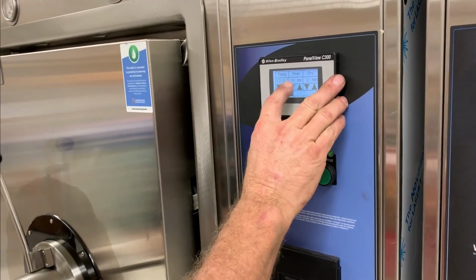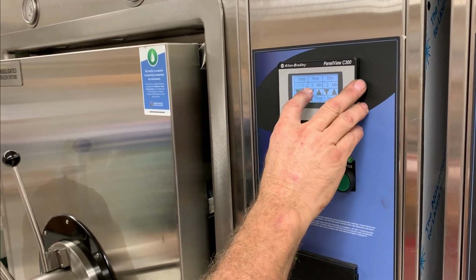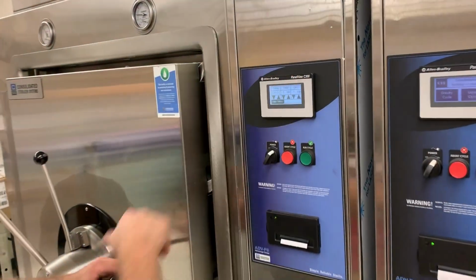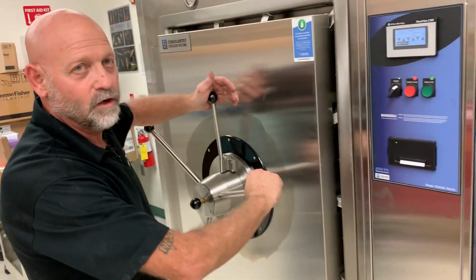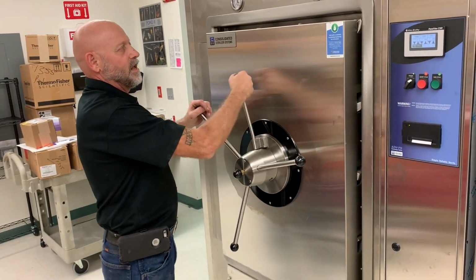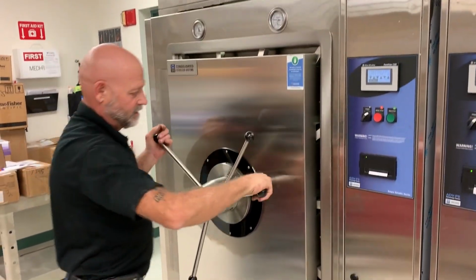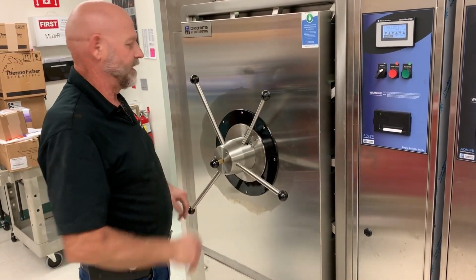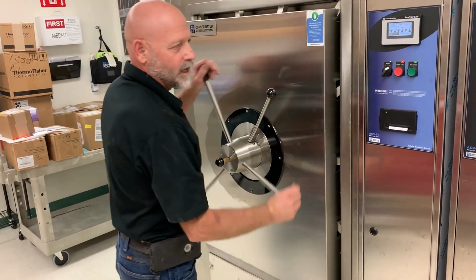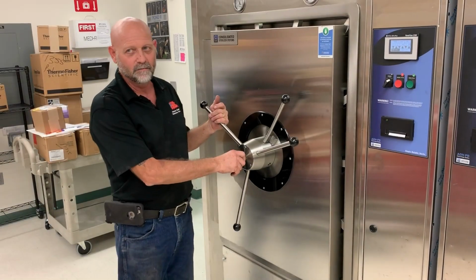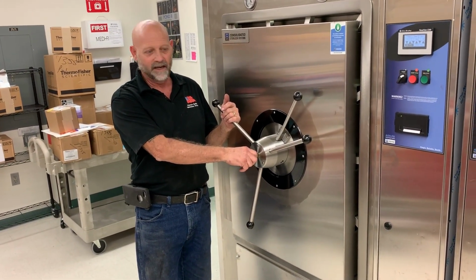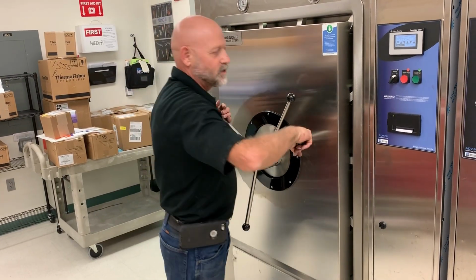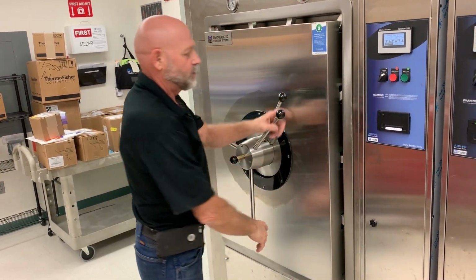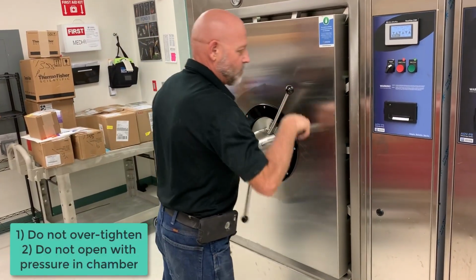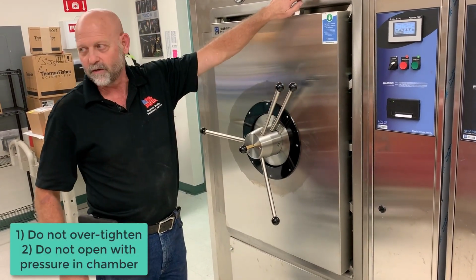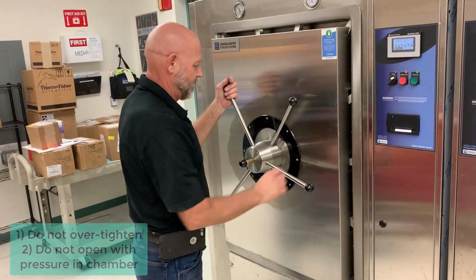So what we'll do is a practice run. I'll do a 1 minute run. Okay, we're going to run this cycle. So what we want to do is close this handle there. That locks the splines in place. Then we're going to close the door, kind of like a big safe. Now we don't want to do this too tight. This mechanism costs $1,000. It's just brass. It's very easy to break. So, two things: you don't want to tighten it too far, and you don't want to open it with pressure in the chamber, ever. This is a safety.